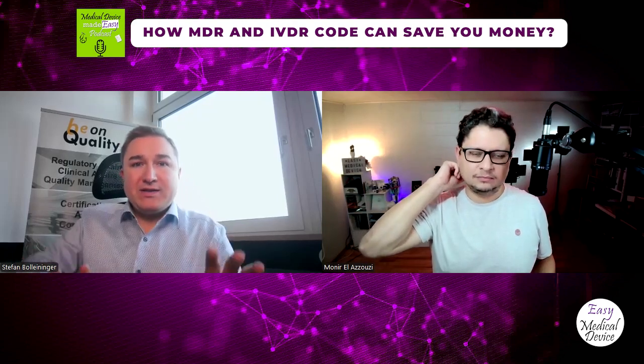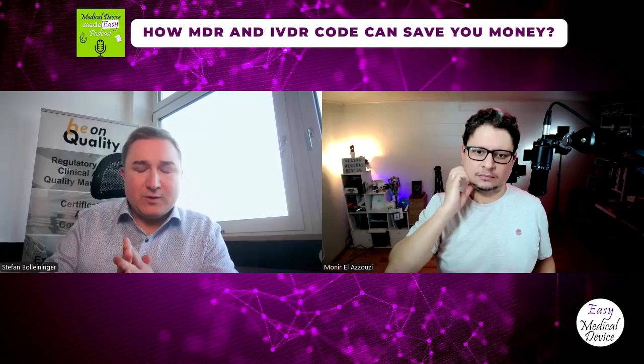Sure. We need to, at that point, distinguish between two different code setups. One, that's the easier one, is the so-called MDA, MDN, MDS, and MDT codes. Those are the ones which are relevant for your certification pathway. The MDA or MDN codes are either for active medical devices or non-active medical devices. That's what the A and the N stand for. And these group your product based on the purpose of your product, what it can do or what it should do. And that makes your life easy for certification approaches.